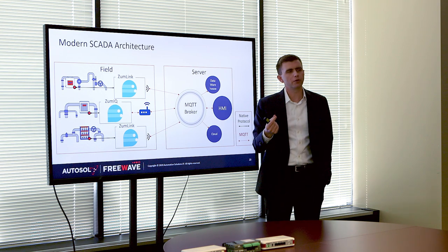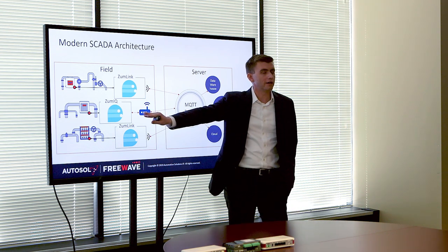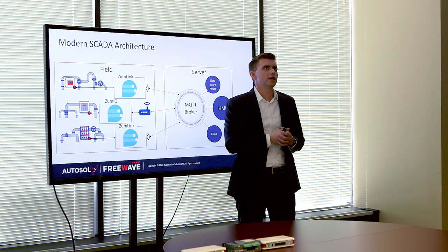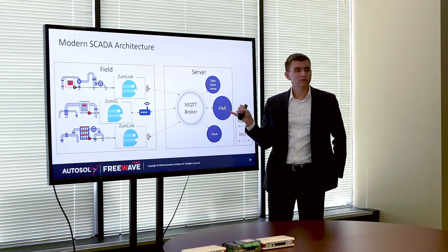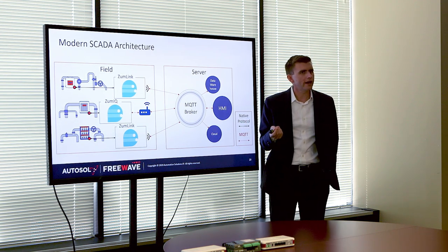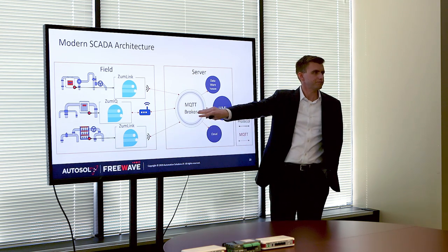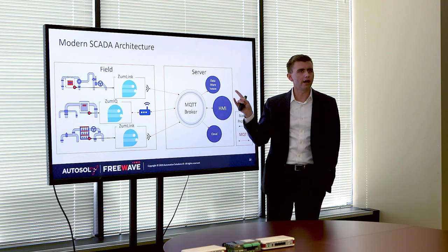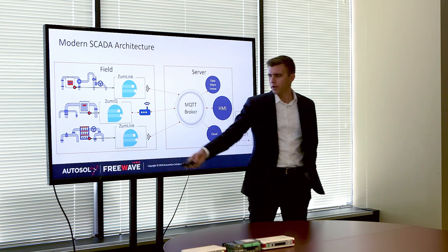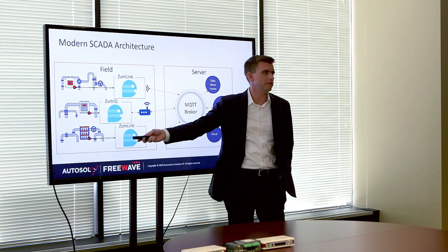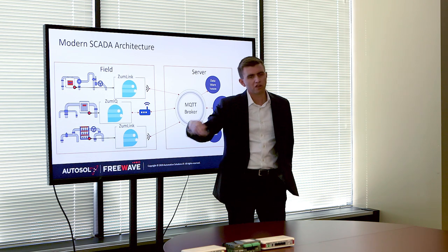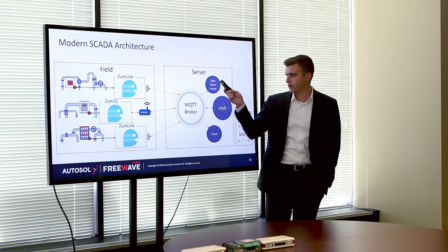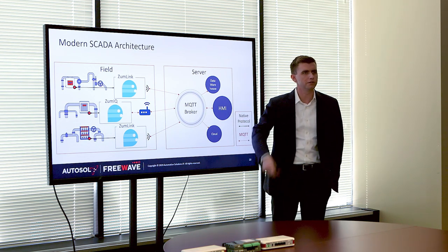This addresses some pain points of poll-response. The first is reduced bandwidth consumption because we're only sending out what's changed. With Edge ACM you can set dead bands and alarms, and for example at a compressor station with 9,000 tags, your HMI doesn't want all 9,000 — maybe 200 to 300. Edge ACM can send all 9,000 tags to the broker; the HMI subscribes to just the couple hundred it wants, and all 9,000 can be dumped into the cloud or your data warehouse. Multiple clients can consume the same data simultaneously because you can add context to the point in the field with metadata and templates in SparkplugB.